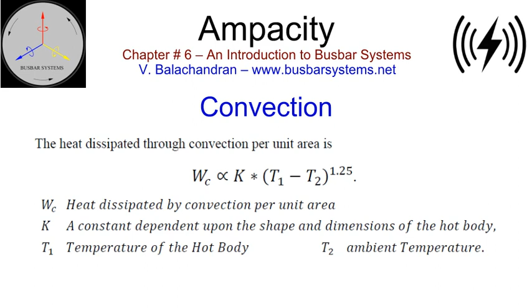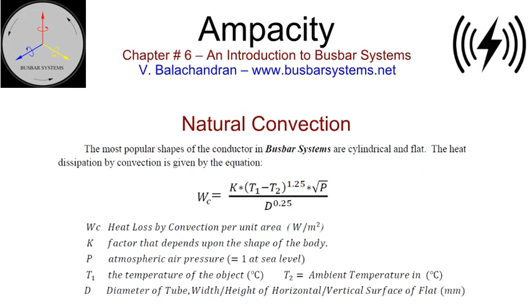The most popular shapes of the conductor in busbar systems are cylindrical and flat. The empirical formulae have been further developed considering the ambient pressure and the dimension of the body. The values of the constants for a few of the configurations are as follows. K equals 7.66 for vertical surface. K equals 5.92 for horizontal surface. K equals 7.66 for round tubes and cylinders.